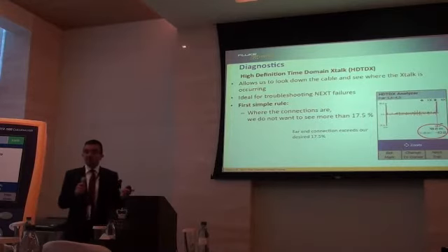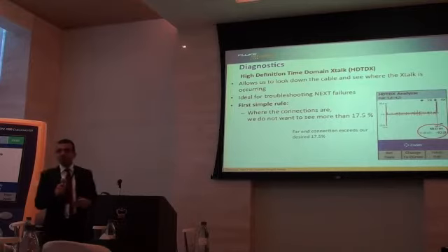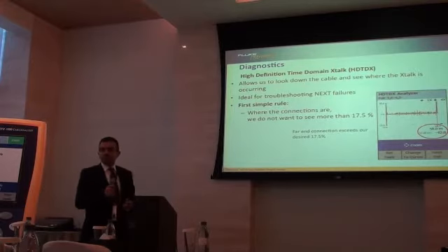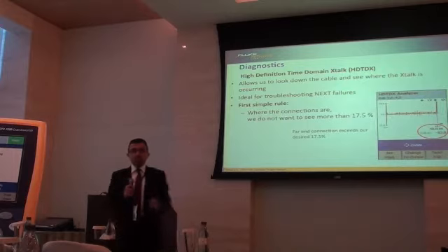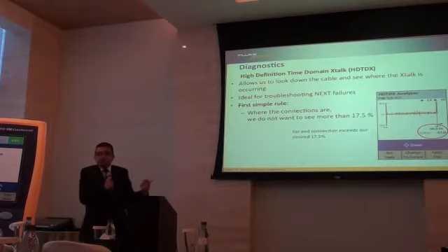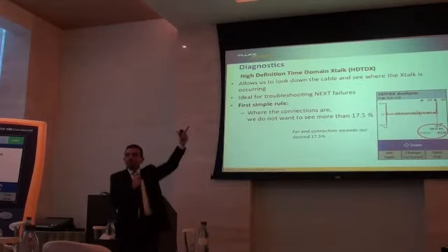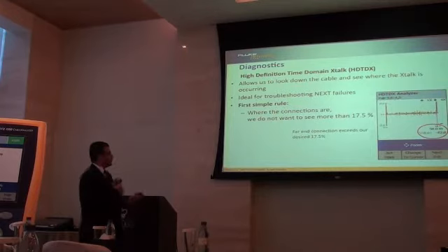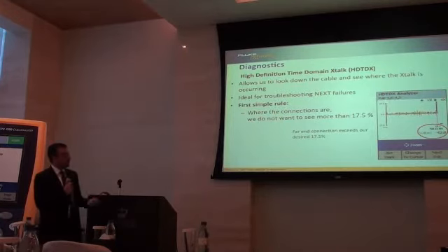This is how you decide that you need to re-terminate the connector at the other end or replace the connector. This is how you identify the fault. So you don't re-terminate the connector at the main, which does not need a re-termination. It is good. It's not bad. The bad is at the other end. This is on the connector side.